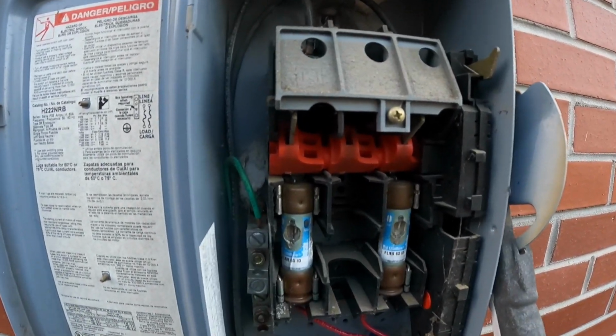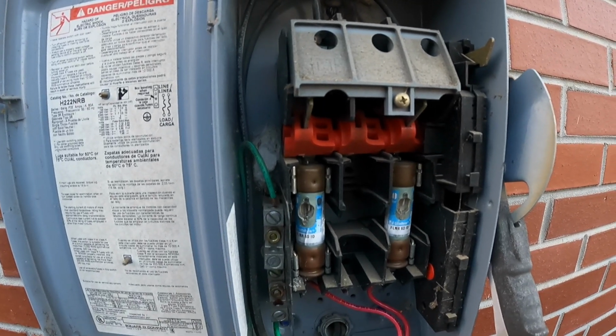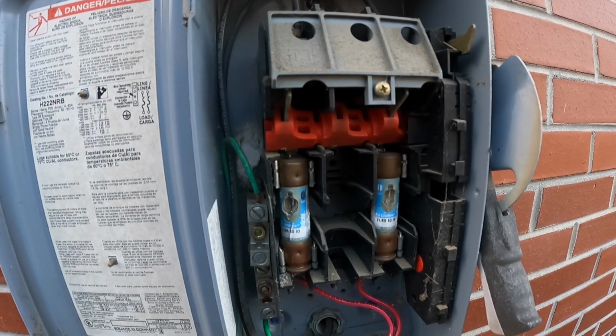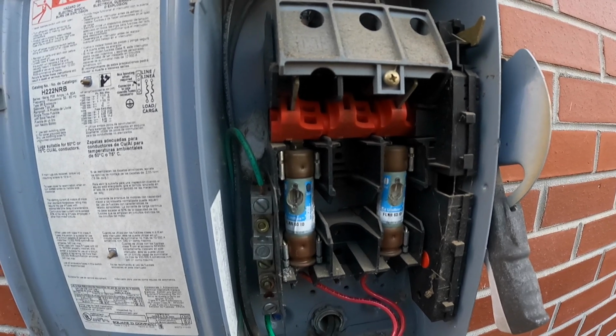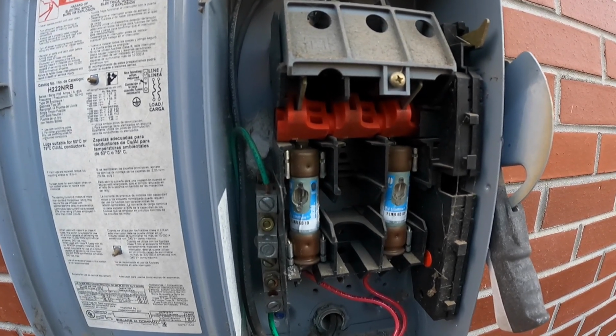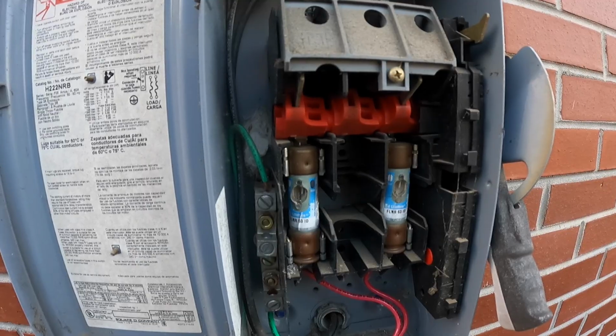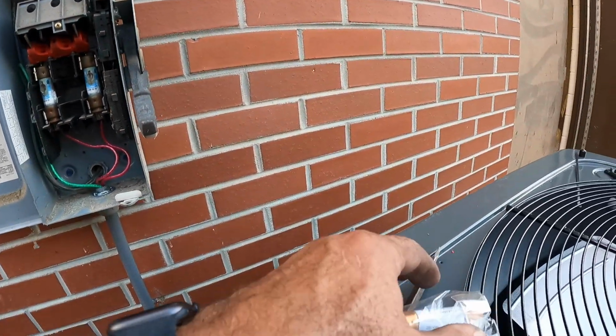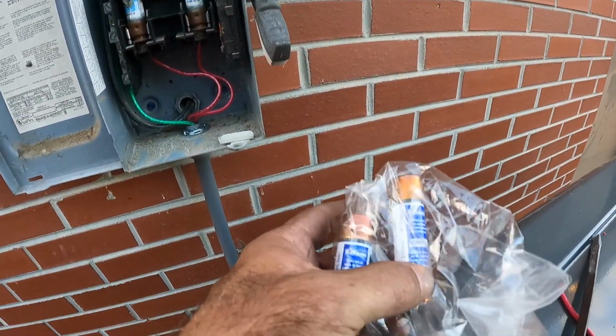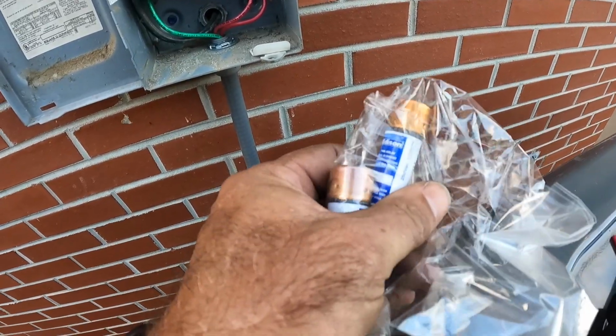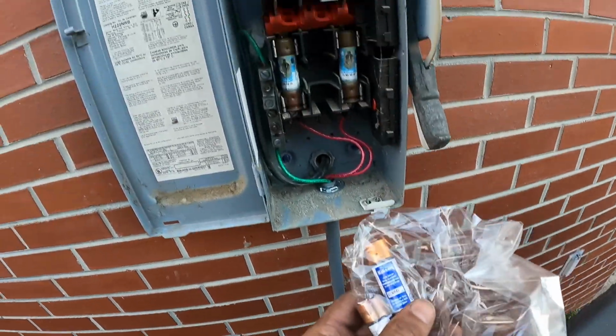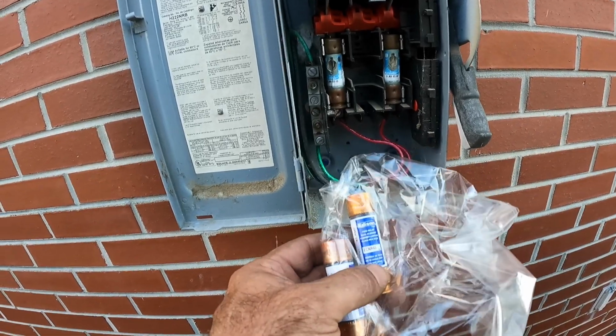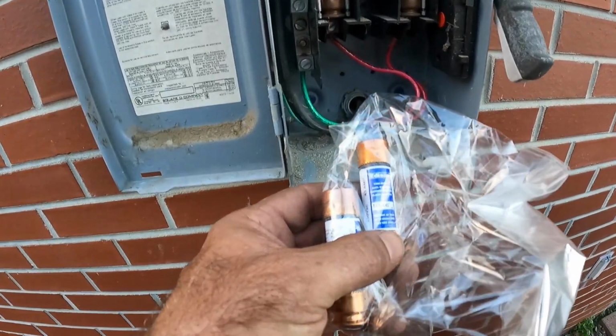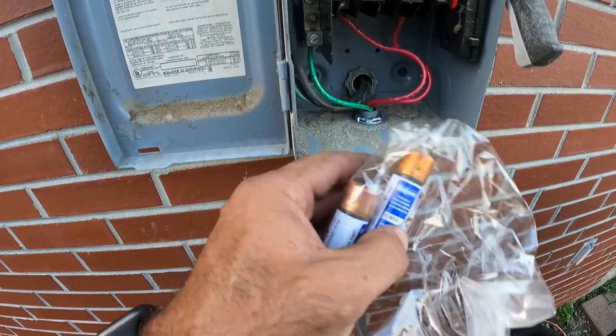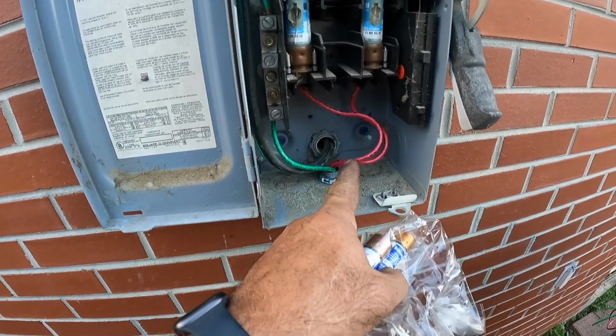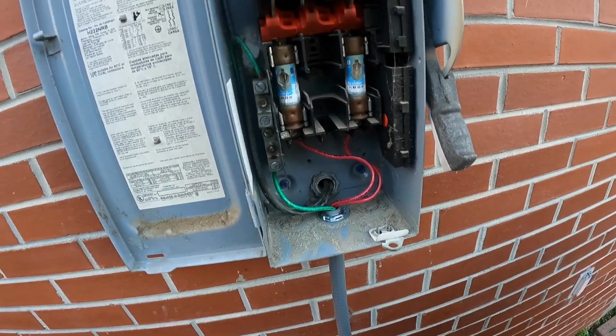These 60 amp fuses are really just for the disconnect. It's got a 50 amp breaker, but I don't know if you can get a 50 or 45 amp breaker for those Square Ds right now. Probably not. But since it had a fuse block out here, I just went ahead and ordered some 45 amp dual element fuses. So that way we've met the rating exactly. We've got the 45 maximum and we've got the 26.2 minimum. And that's how you do it.